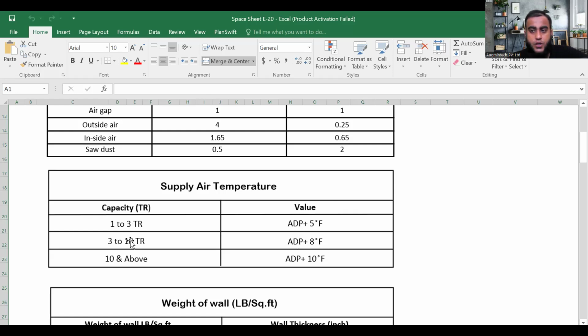Suppose let's say you have done the cooling load calculation and you have got the value around 10 ton or 9 ton, let's say 10 TR. Okay. So for 10 TR, if you want to calculate the supply air temperature, see the formula is written: apparatus dew point temperature plus 8 degrees Fahrenheit. So calculate the apparatus dew point temperature. For that also we have a long procedure. Okay. So in heat load calculation, we are teaching this thing. So here normally I have shown you, this is the way to calculate the supply air temperature. Now I think all of you get the idea.